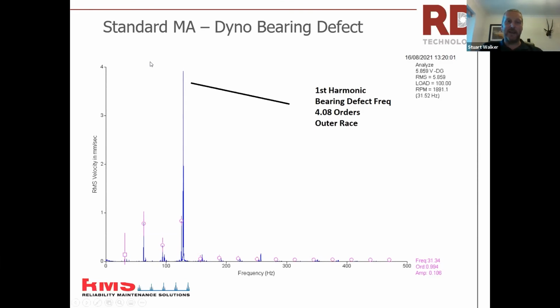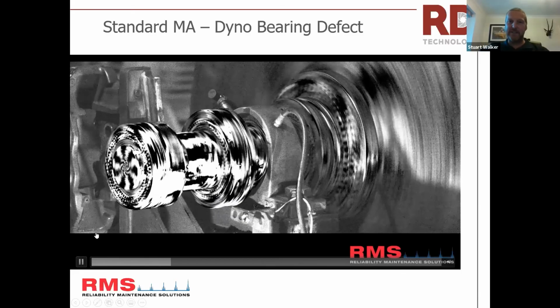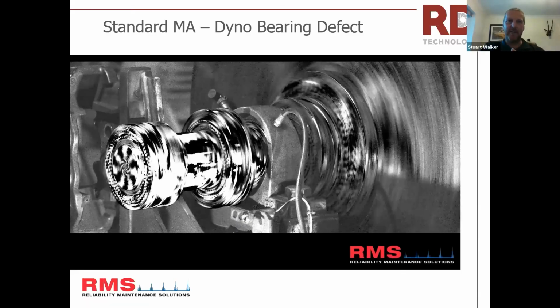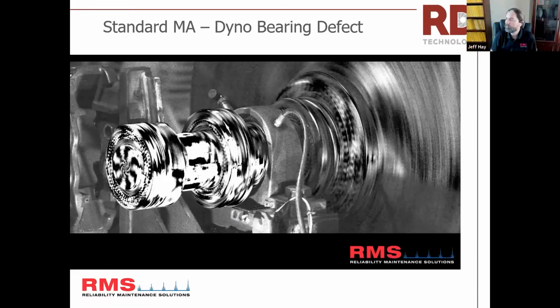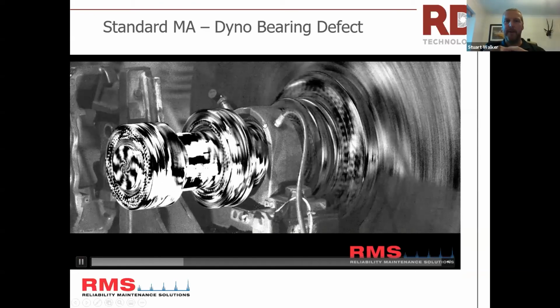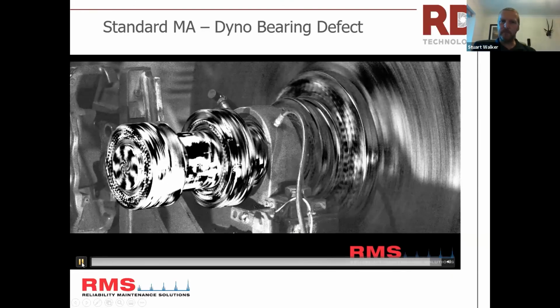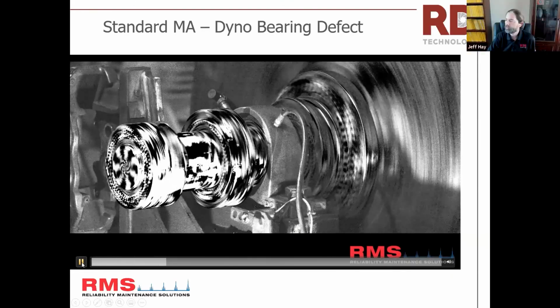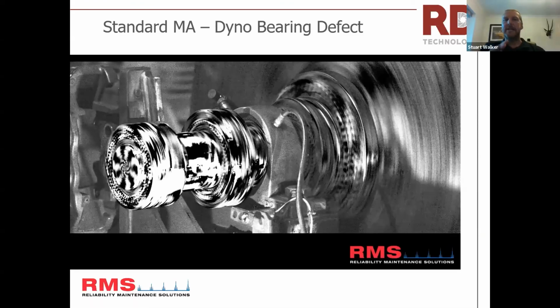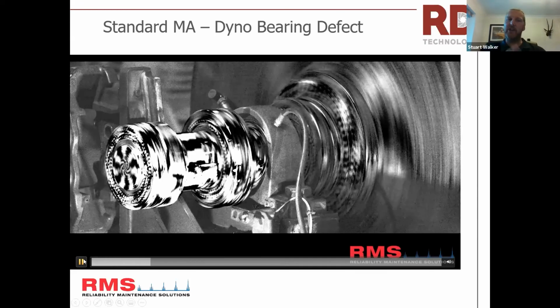And I'm still trying to get my head around this one when we see it. So this is filtered to that 128 hertz. Look at the bearing. It's almost squashing up and down like a tennis ball. It's really flexing. Unbelievable. Yeah, it really is. That's a bearing frequency we're looking at. So the guys there, they're pulling the bearing out, and we're going to check for two things.